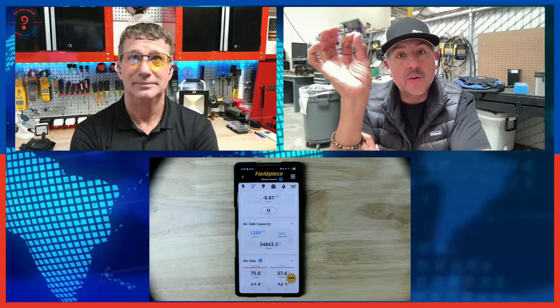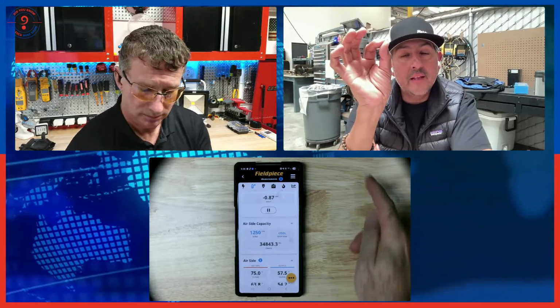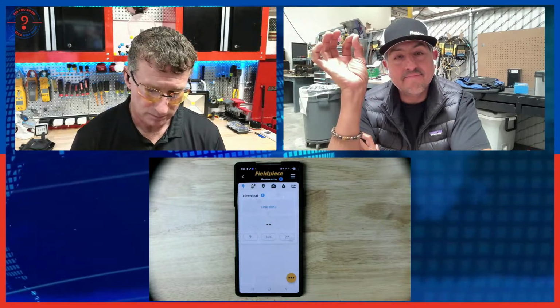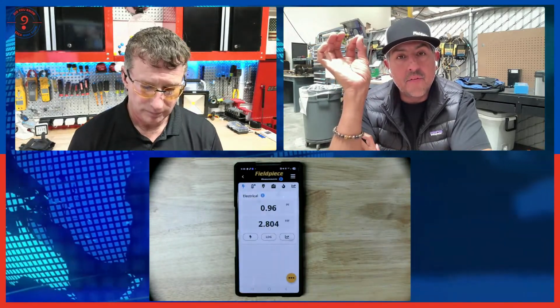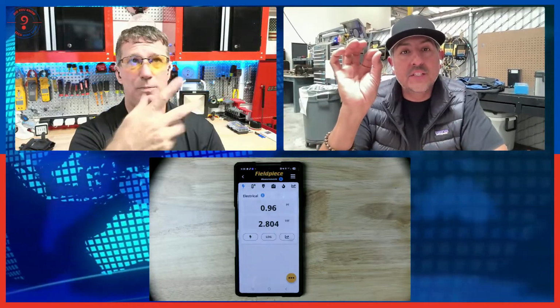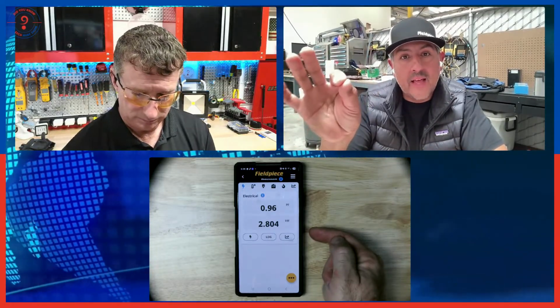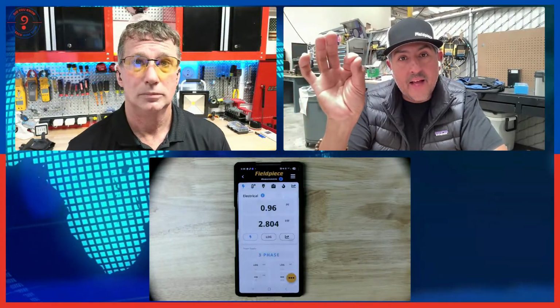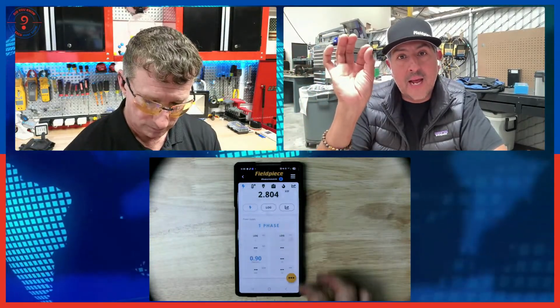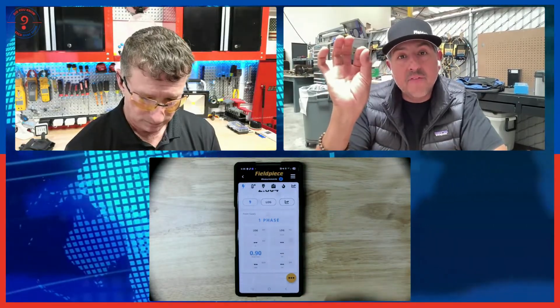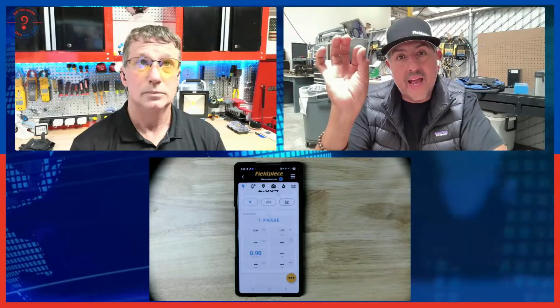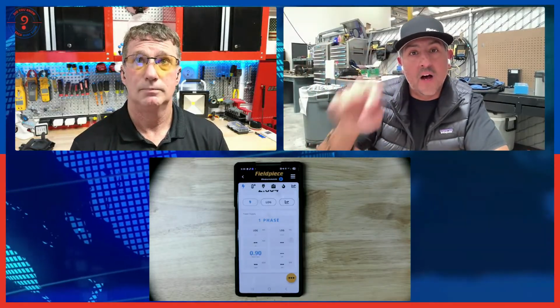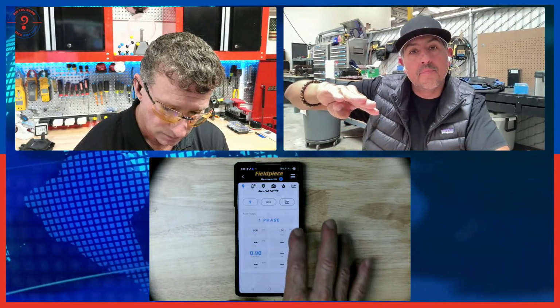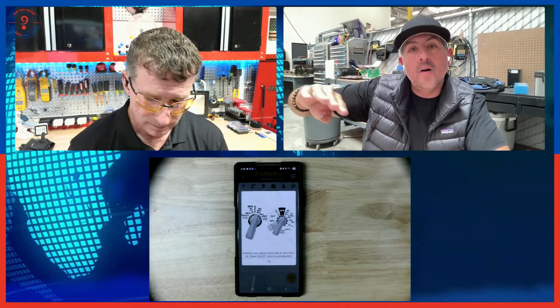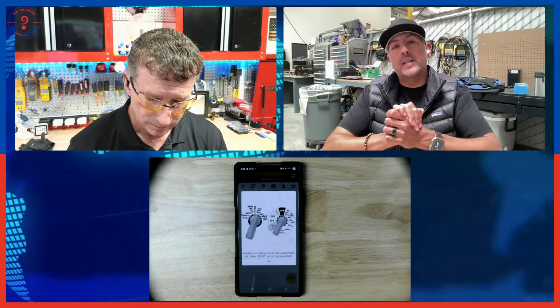Now if we want to turn that into efficiency, go back into the lightning bolt. To do an efficiency test, press the lightning bolt under the numbers. That starts our power and efficiency test. Tap that to single phase. Right now you have the meter on L1, L2 measuring volts and amps on L1. We'll press log because that's what that first row is asking for, the log button at the top. Oh, you know what? We don't want to be on power. We want to be on volts and amps to run this test.